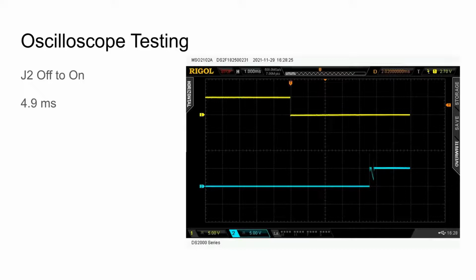So, what are we looking at in this oscilloscope trace? First of all, this is connected to relay J2 as I turn the relay from off to on. The top yellow trace is the voltage at the bottom of the relay coil. The other side is connected to 5 volts. The channel is set to 5 volts per division. So when it switches from the higher to lower, it's turning the relay coil on. Note that the scope is set to edge trigger on this channel at 2.5 volts. So that's how it ends up in the middle of the screen.